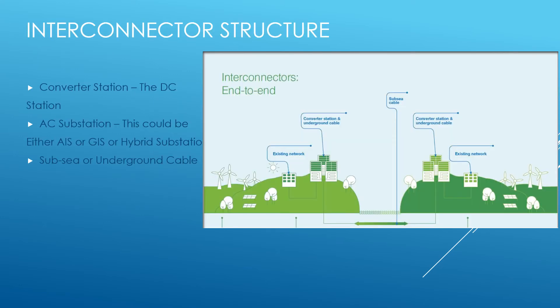Our next slide covers interconnector structure. This shows a typical structure of an interconnector between two countries. As you can see on the screen, the interconnector has a very high voltage cable between the two countries. In this case it's a subsea cable. On either side of the country there is a converter station, also called a DC station, an AC substation which could be AIS, GIS, or hybrid, and a subsea cable going below the seabed.